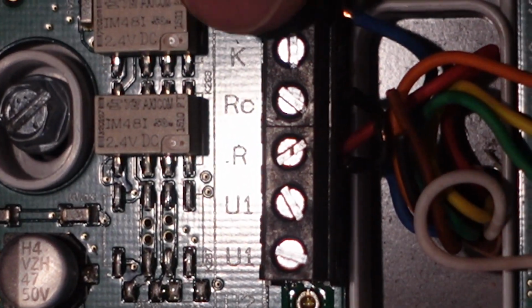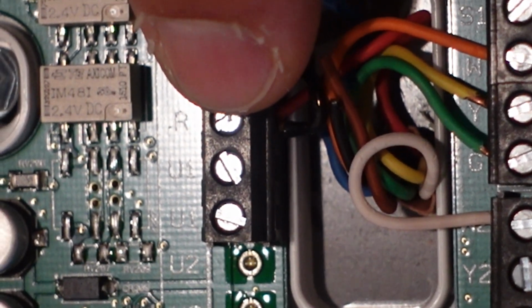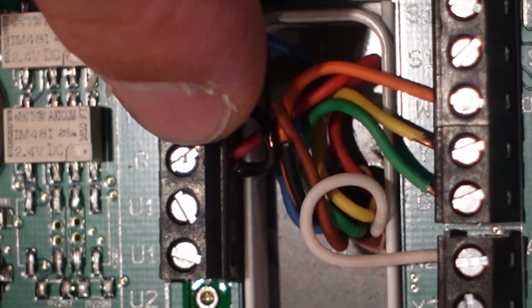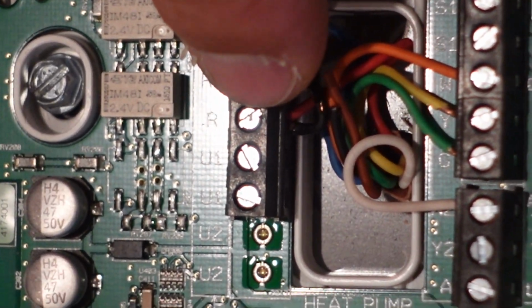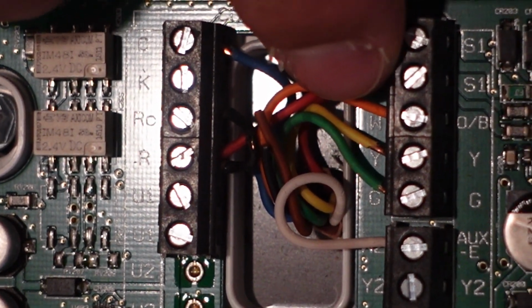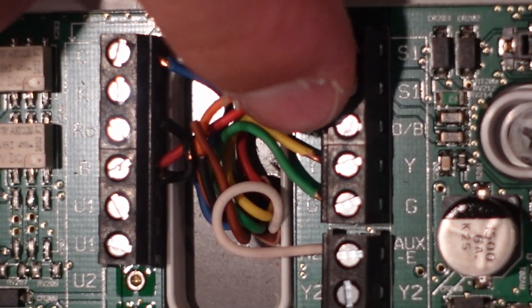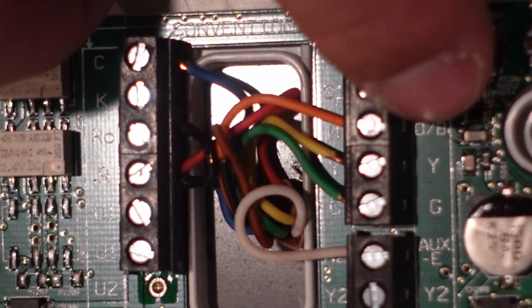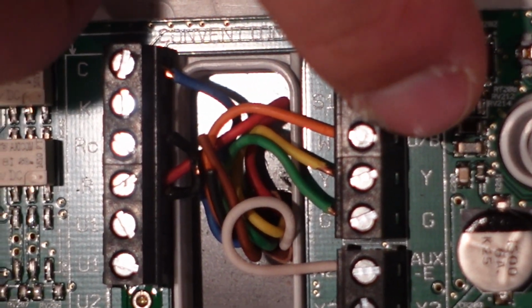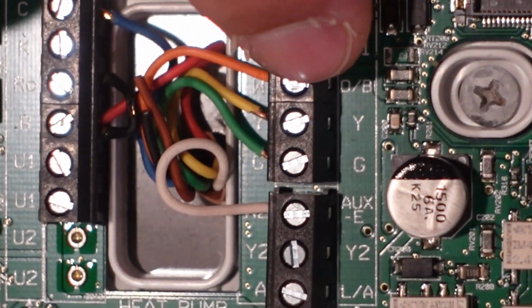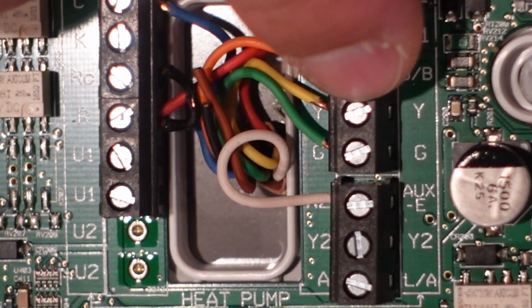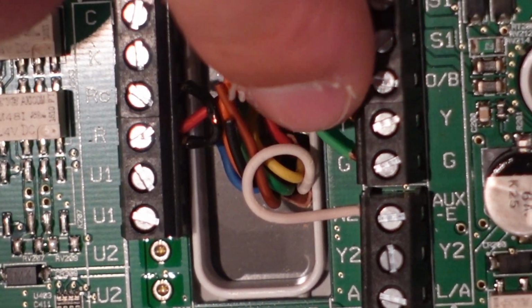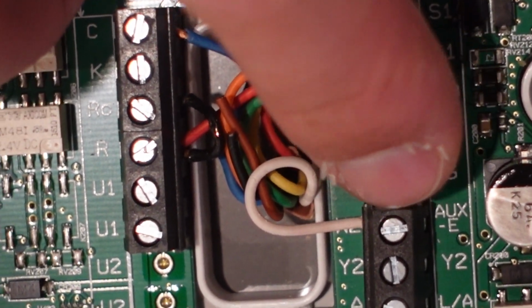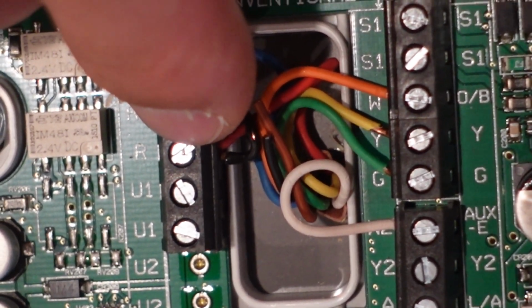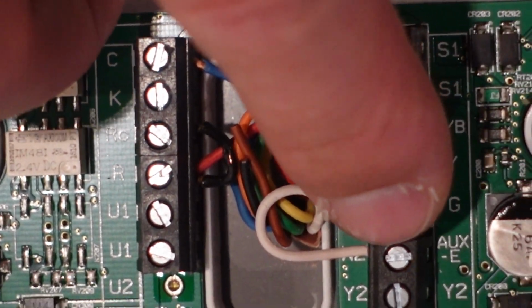There we go. So this is my R terminal right here, R terminal right there. Got my red wire connected to there. There's my common terminal. And what happens on a thermostat is that R comes in, and then depending on what the thermostat is set to, it sends signals down these wires. So O, which is my orange wire, O terminal. The B is used only in the case of powering the reversing valve in heating instead of in cooling. So O is for cooling, B is for heating. Then we have our Y terminal right here, and we've got our G terminal, which is our indoor fan signal, and then our W, which is our heat kit. So all that happens is power comes in here and then transfers across to any of these terminals that are needing to be engaged.